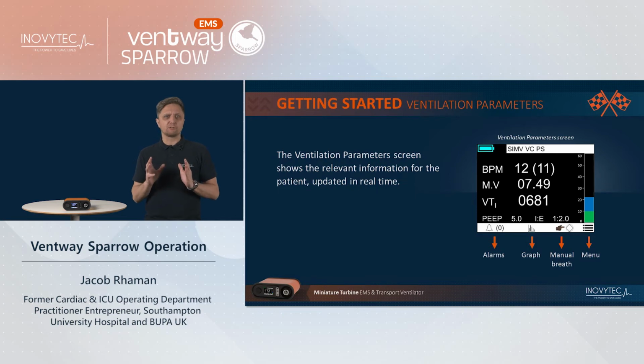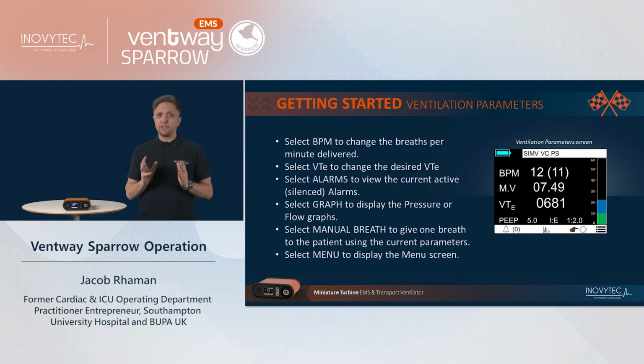The ventilation parameter screen shows the relevant information for the patient, which is updated in real time. You can select BPM to change the breaths per minute delivered, select VTE to change the desired VTE, select alarms to view the current active or silenced alarms, select graph to display the pressure or flow graphs. Select manual breath to give one breath to the patient using the current parameters. And finally, select menu to display the menu screen.